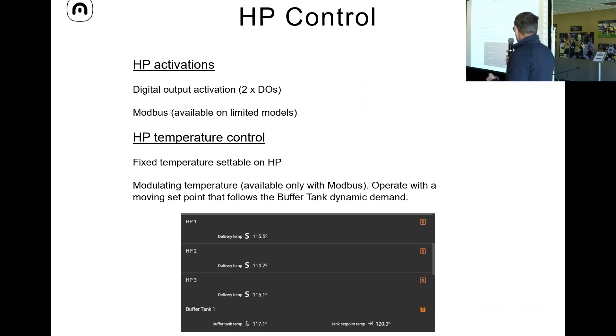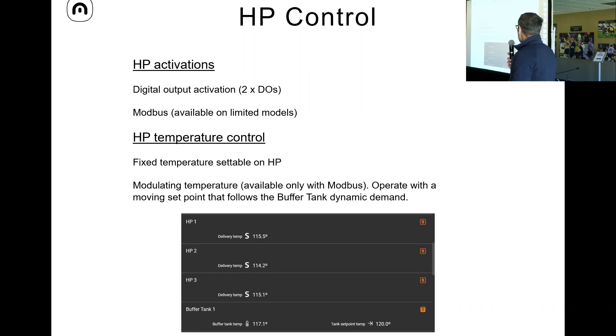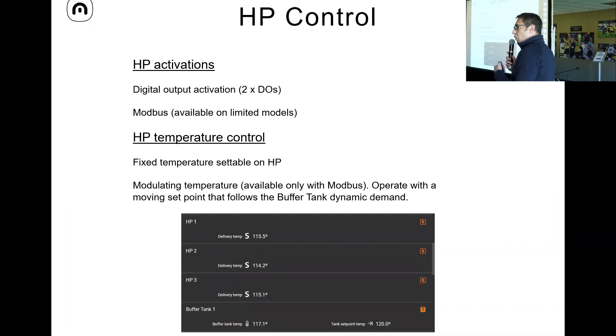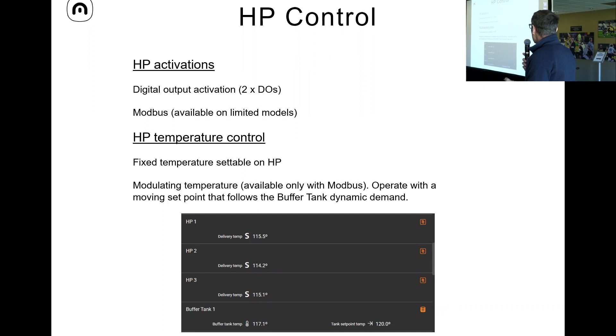Otherwise it would be a digital output activation — on/off, heating and cooling, fixed temperature. Controlling the heat pump via Modbus is an enormous advantage because we can modulate not only the temperature on the buffer tank, but also the temperature of the heat pump itself. That allows us to achieve quite a bit of saving and increase the COP of the heat pump in both heating and cooling.